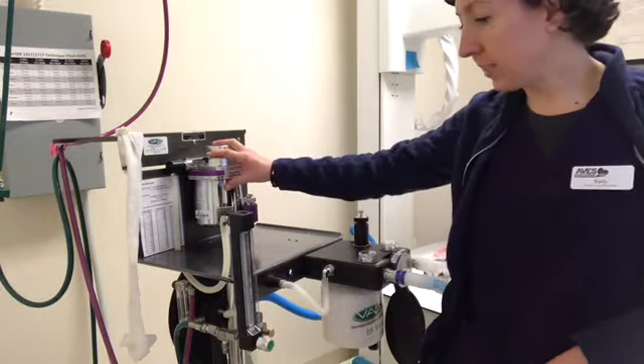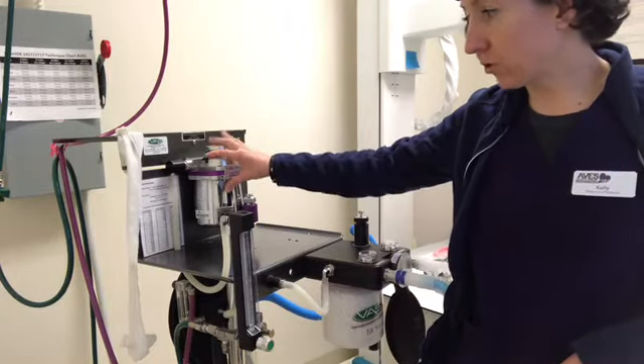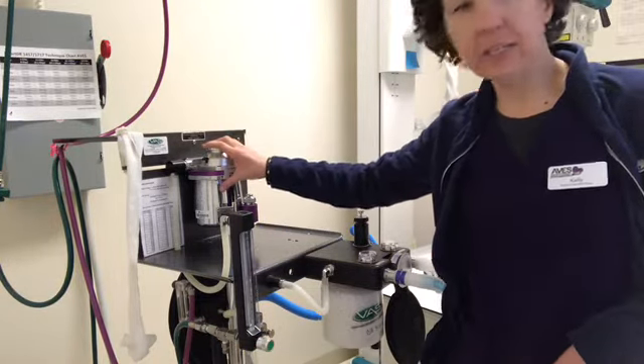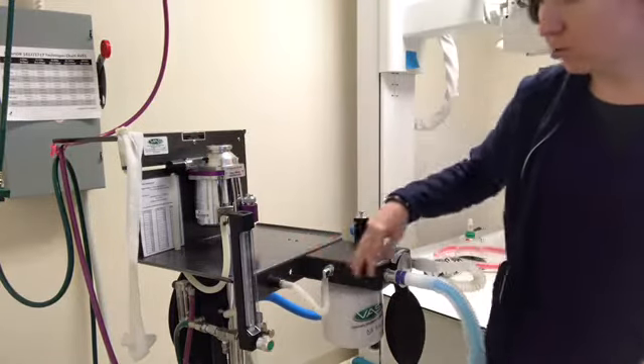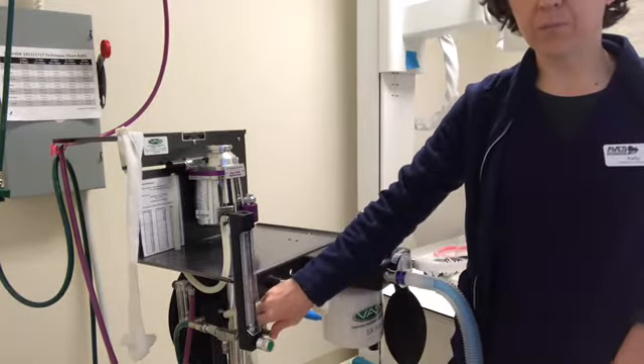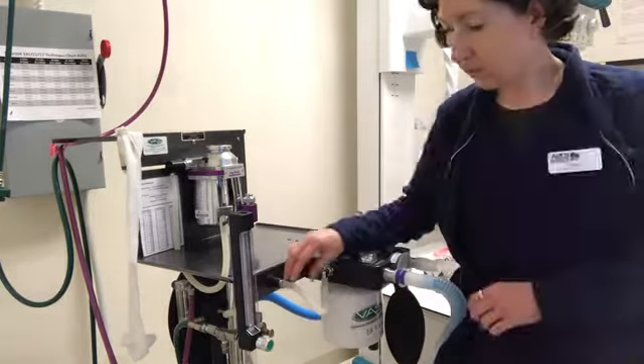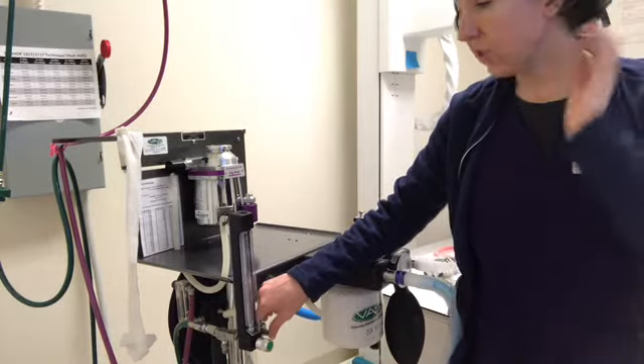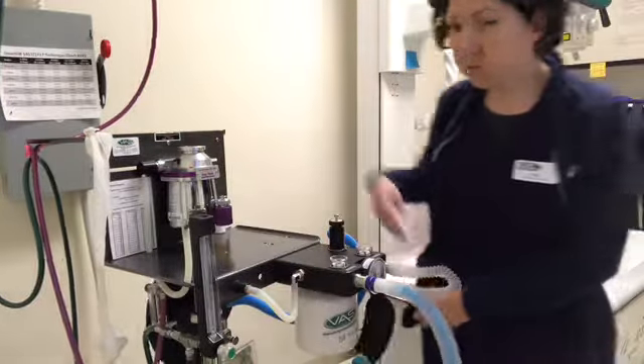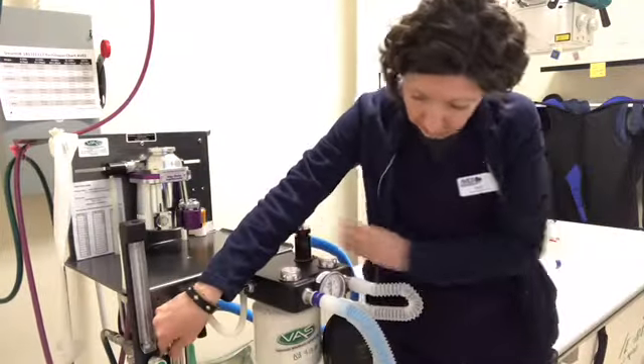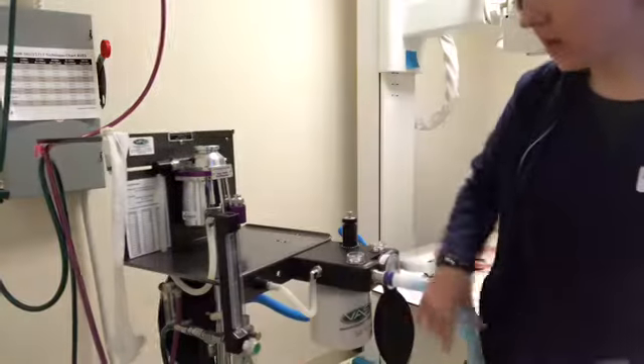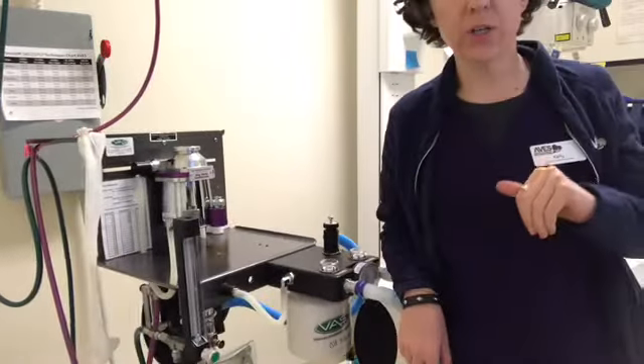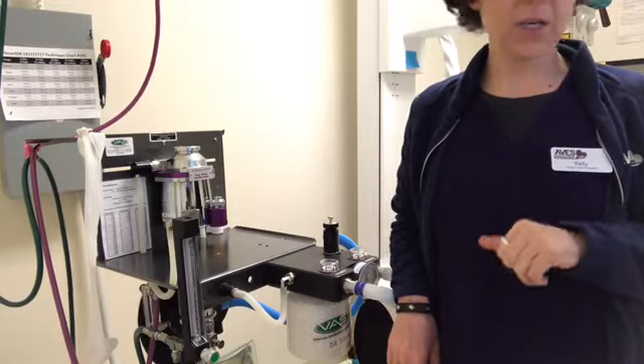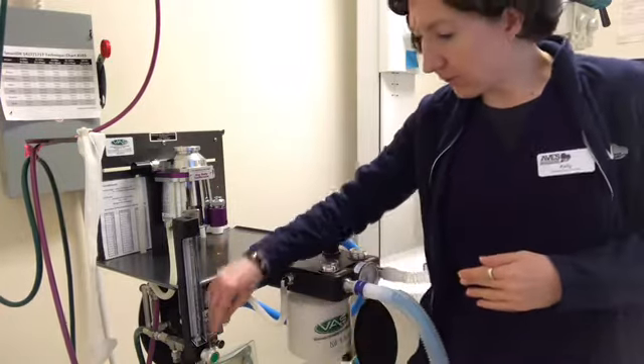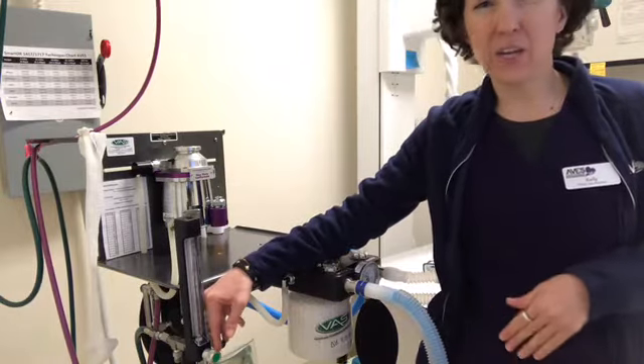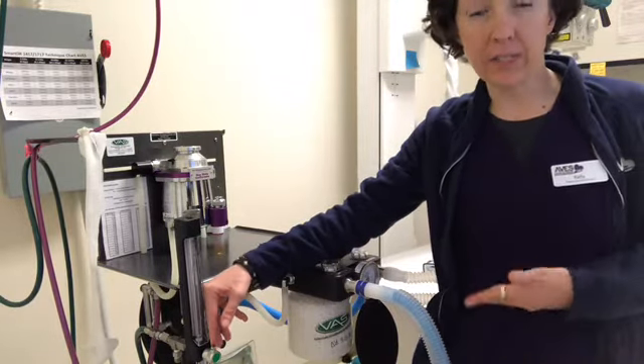It bypasses the vaporizer, so there's no anesthetic being pumped through when you hit the flush valve. The flush valve feature is used to rapidly inflate a reservoir bag, or to get oxygen to a critical patient very quickly. The flow rate of this flush valve is approximately anywhere between 35 and 75 liters per minute.